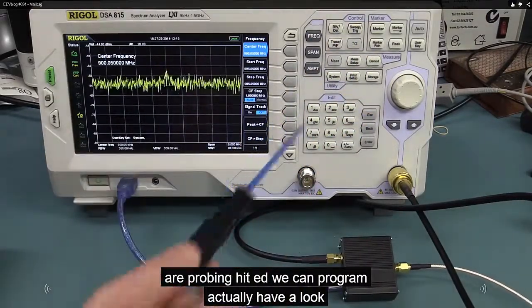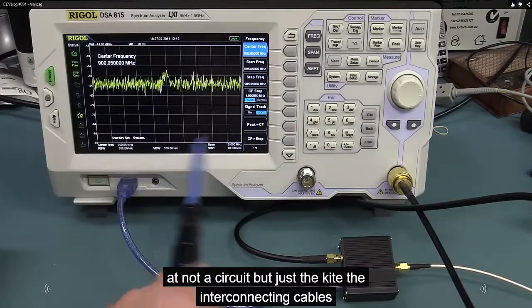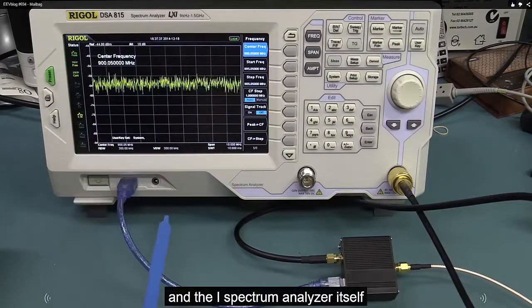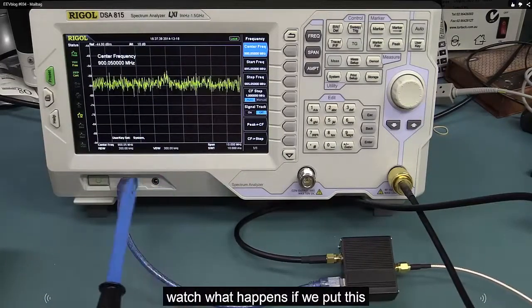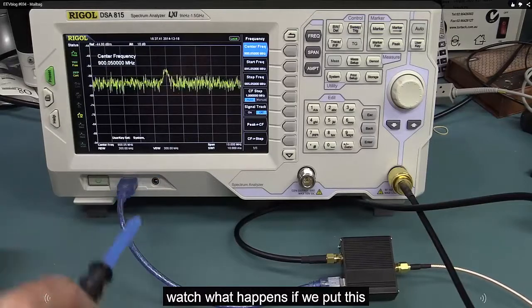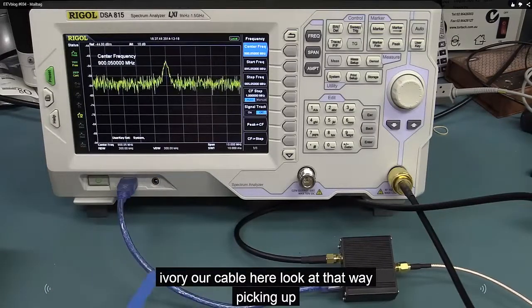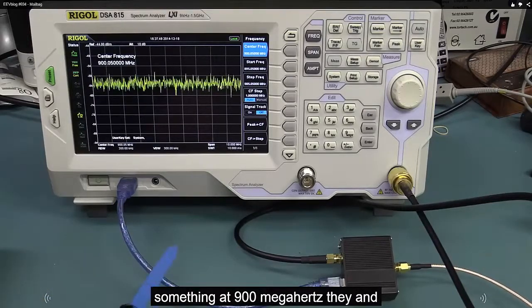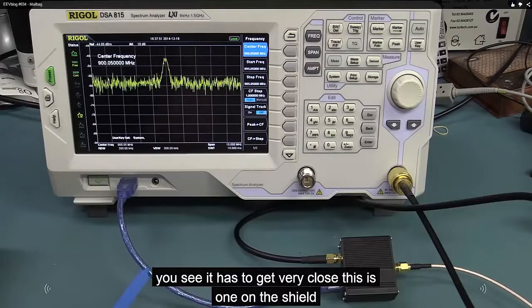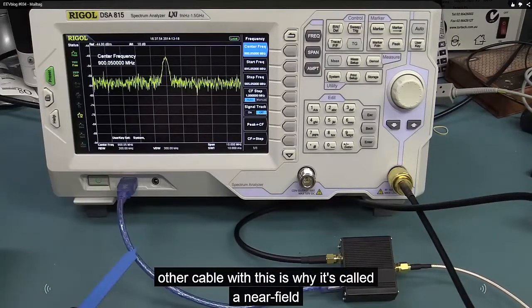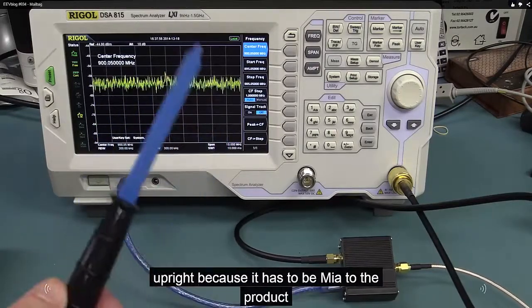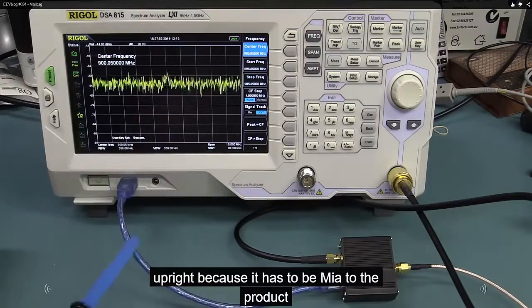I've got my E-field probe in here, and we can probe around and have a look at not a circuit, but just the interconnecting cables and the spectrum analyzer itself. Watch what happens if we put this over our cable here. Look at that. We're picking up something at 900 megahertz there, and you see it has to get very close. This is on the shield of the cable here. This is why it's called a near-field probe, because it has to be near to the item that you're trying to test.